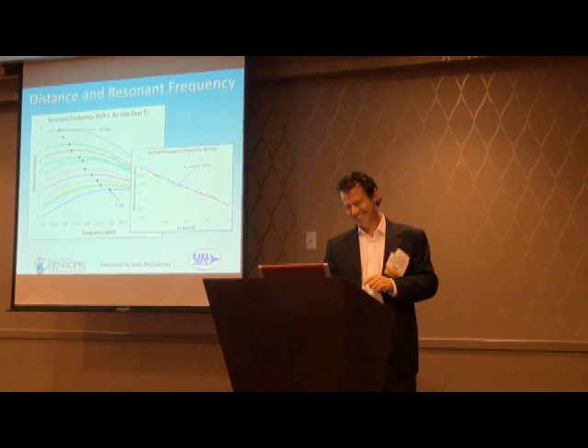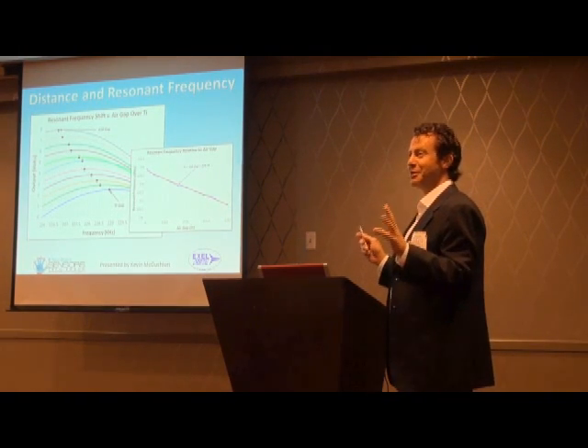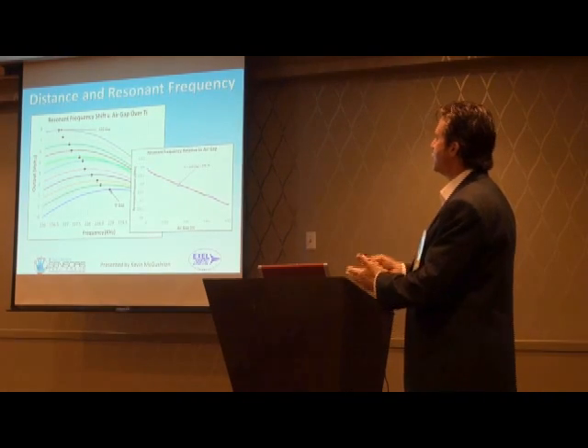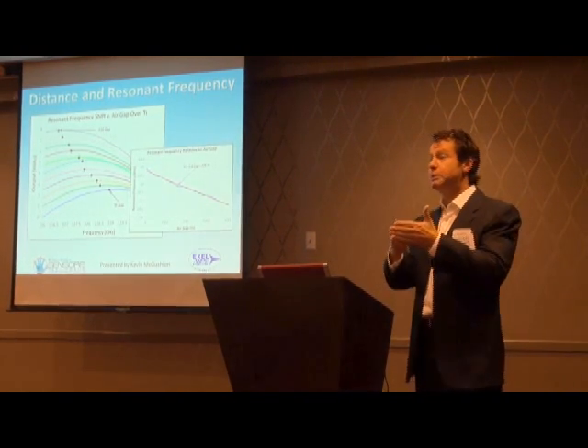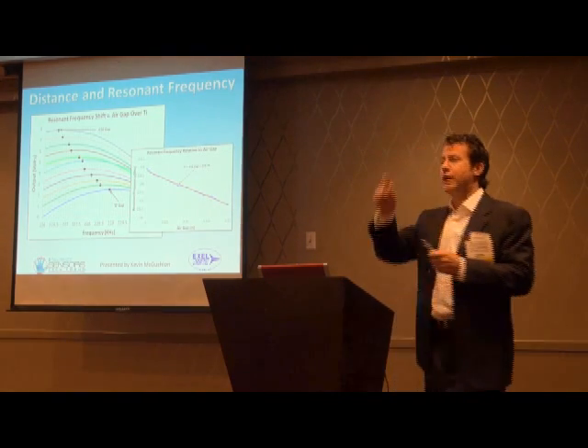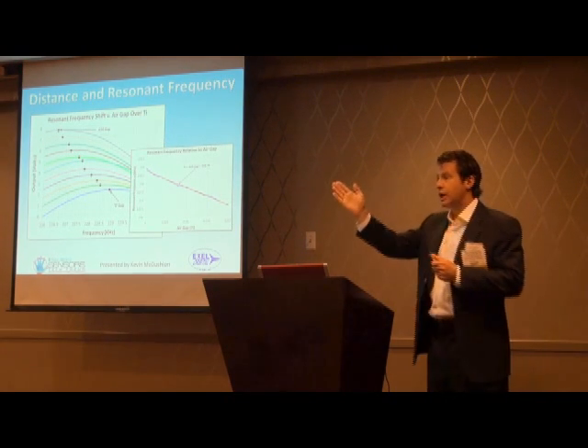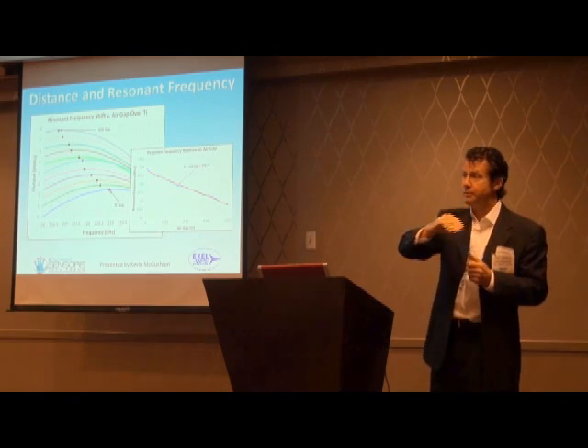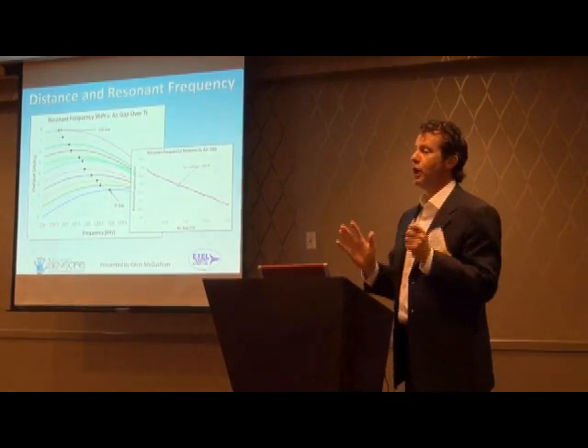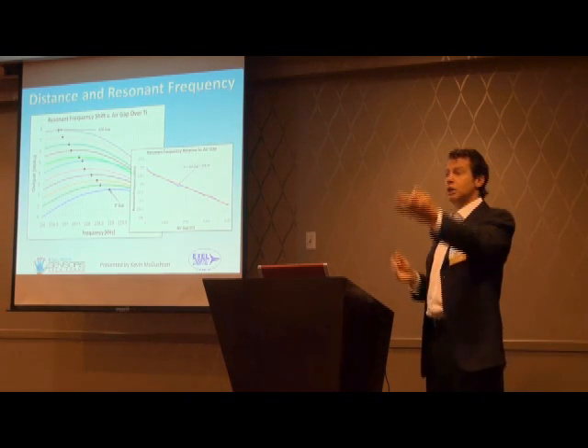Another curious thing that happens with the sensor: as we park it in front of a target — say a piece of titanium, or composite, or aluminum — and move the sensor away, that resonant frequency shifts to the left, to lower frequencies. You can directly relate that frequency shift to distance, which is important because quite often you'll be scanning something with variability in air gap — variability in the distance from the sensor face to the target.